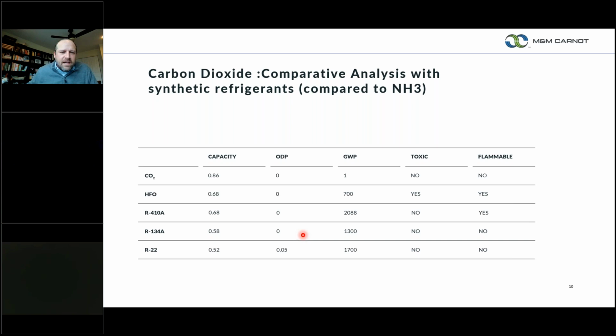But one of the things I like on this chart is it shows the capacity of CO2 as a refrigerant. Compared to ammonia, it holds about 86% of the amount of heat that ammonia holds. Compared to the synthetic refrigerants, that's a little bit more. This becomes important because you need less refrigerant to move the same amount of heat than you would need in a synthetic refrigerant-based system. So what had happened was our president, Marc Andre, was out giving presentations on the benefits of CO2 refrigerant for industrial refrigeration applications.